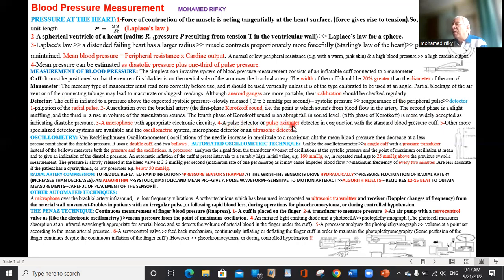Of course, we can use the pulse oximeter with the blood pressure, and we can use a microphone, audible microphone on the brachial artery. And we can, of course, use oscillometric system, and ultrasonic can be also used. The oscillometry, in the beginning, it was manually operated by what we call von Recklinghausen oscillotonometer. It is based on the oscillation of a needle. Whenever this needle amplitude begins to increase, it yields the systolic, and when it reaches its maximum, it yields the mean, and then it begins to slow down, indicating the diastolic blood pressure.